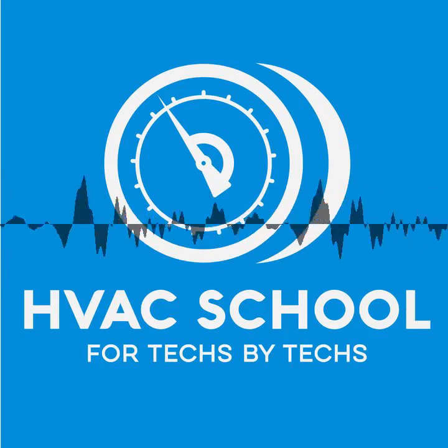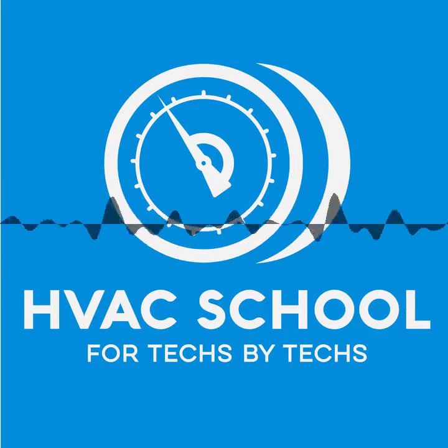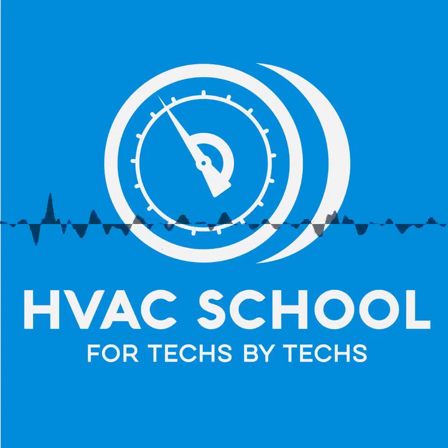And one thing I don't really see too often, though, is the tower loop pumps. They don't usually have a drive on them because they just want a constant volume. Sometimes they do, but a lot of times they don't. They don't worry about putting drives on those tower pumps because they're not really changing the water flow rate through the tower enough for it to make sense in a lot of cases. So what else? What are we missing?